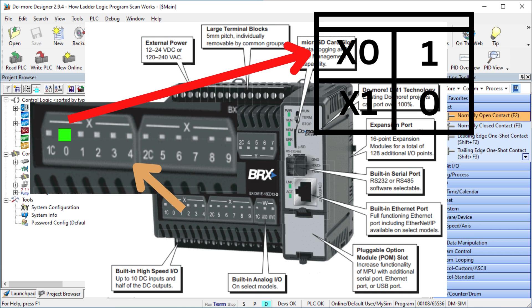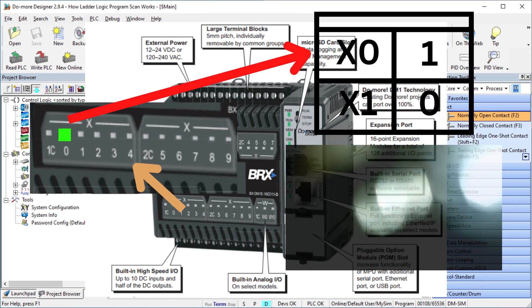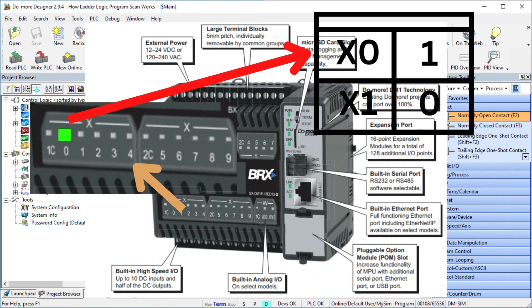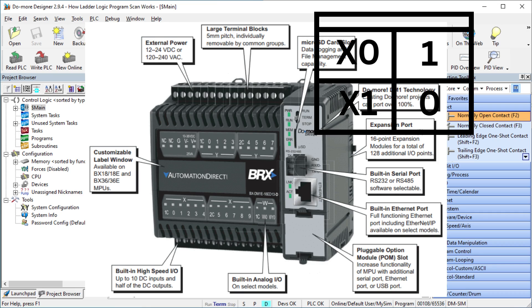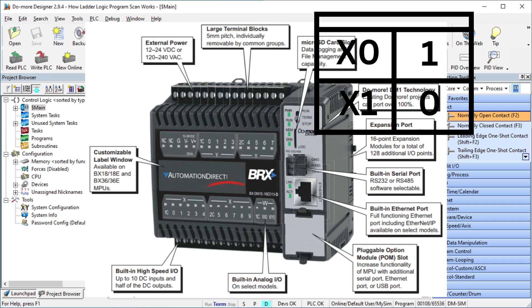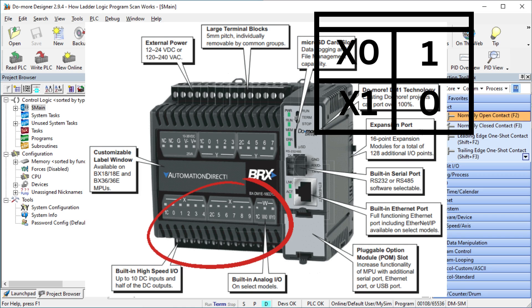Inputs are usually optically isolated from the PLC CPU. This means that the only thing they share is light, which will protect them in the industrial environment. We are viewing the BRICS or BRX Do More PLC. This has inputs built into the main unit of the CPU or central processing unit. As mentioned above, the physical inputs are copied into the memory table each scan.